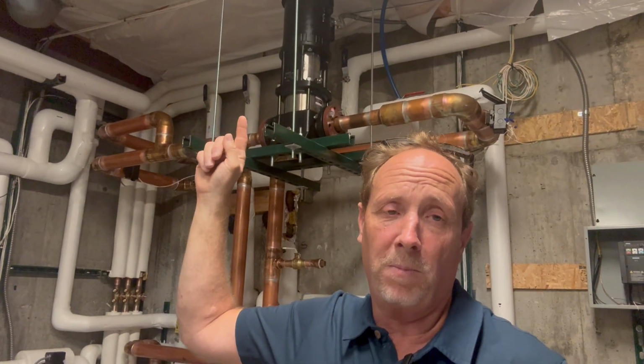So we ended up decoupling the ground heat exchanger from the pumps. The installing contractor bowed out, said, hey, we're out of here. We don't want any more to do with this. So DMA Engineering stepped in. It designed and implemented that big pump that you see up there, a Grundfos CR3 pump that we're using to pump into the ground heat exchanger. And then since we're hydraulically decoupled, those small source pumps will pump into just that side, and then that will pump into the ground heat exchanger and give us the flow that we need.